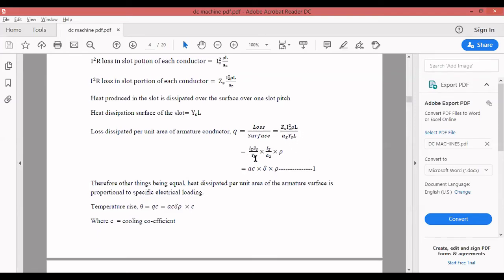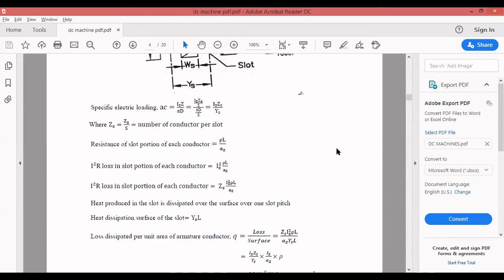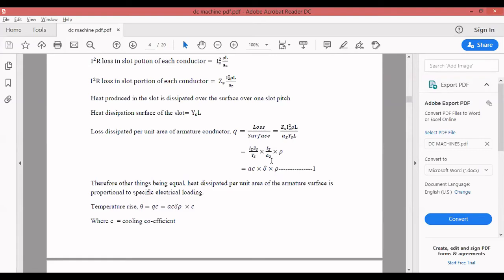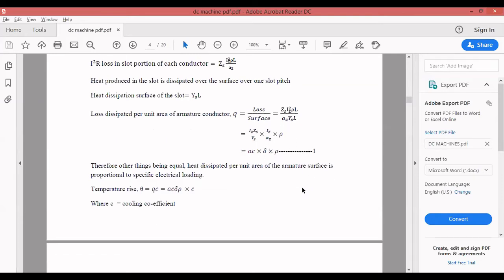For higher rating machines, space left for conductors is only around 40%, so you have to use a small value of ampere conductors — not 30,000 or 40,000, but like 10,000 to 15,000. That is the impact of voltage: based on the voltage rating of the machine, you select the value of ampere conductors. For high voltage machine, select a small value of A_C; for low voltage machine, go for a larger value of A_C.